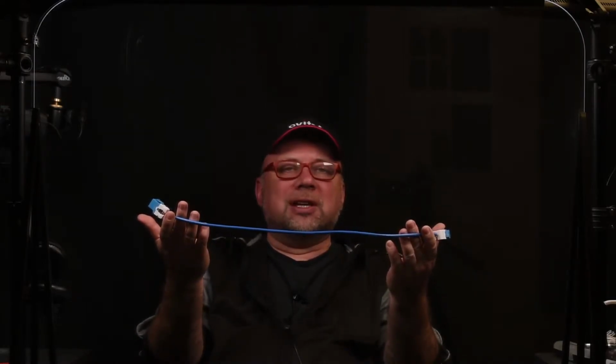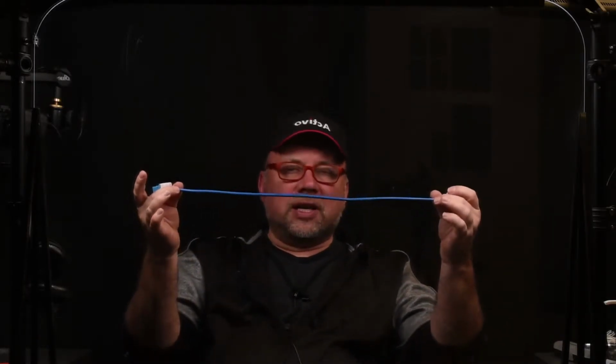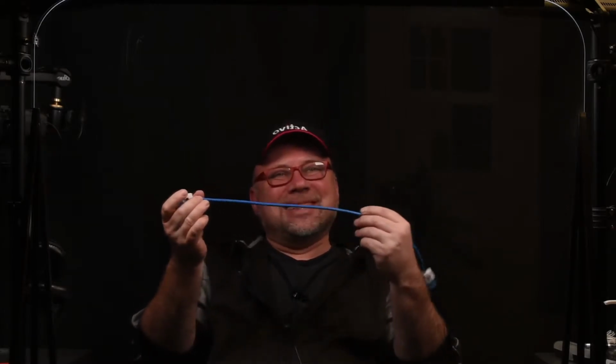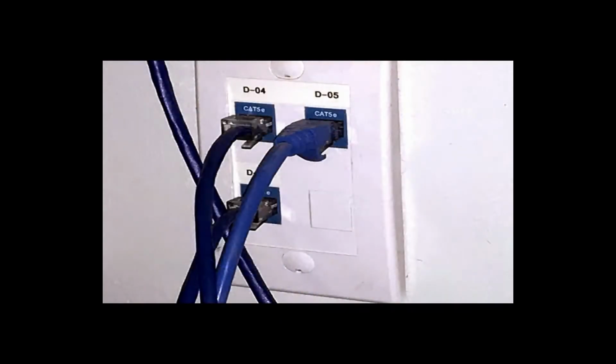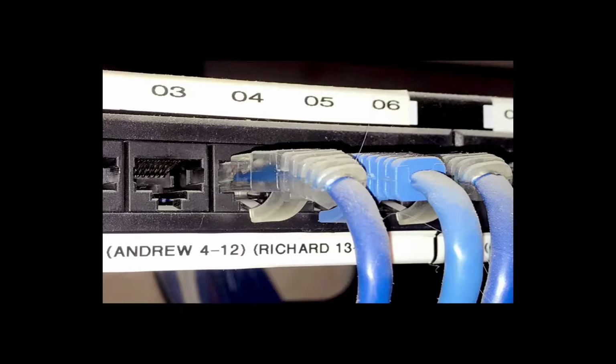just for the reason of simplicity, we just say that data cables should not be longer than 300 feet end to end. Okay? If the cable is longer, then the signal is basically not readable at the other end. Okay? All right. Now let's keep going with this. You see, also the wires are labeled and the data jacks are labeled. So it says D4, D5, and this is probably D6. So if we go back to the patch panel, that's where they are on the other side. Labeling is important. Okay?